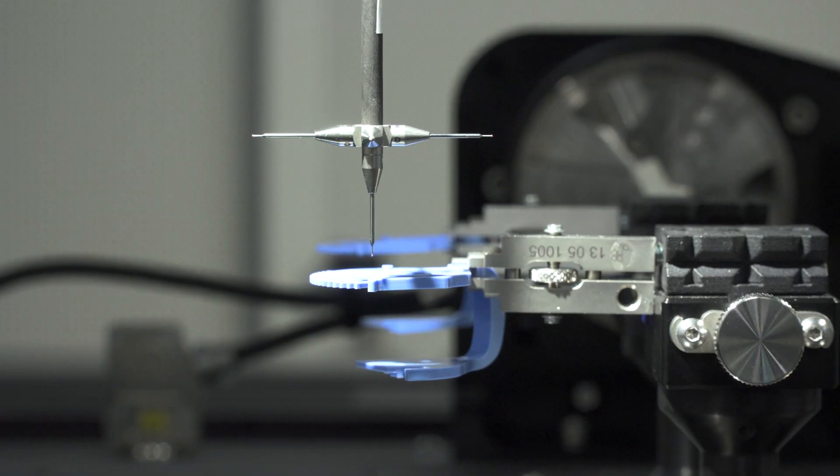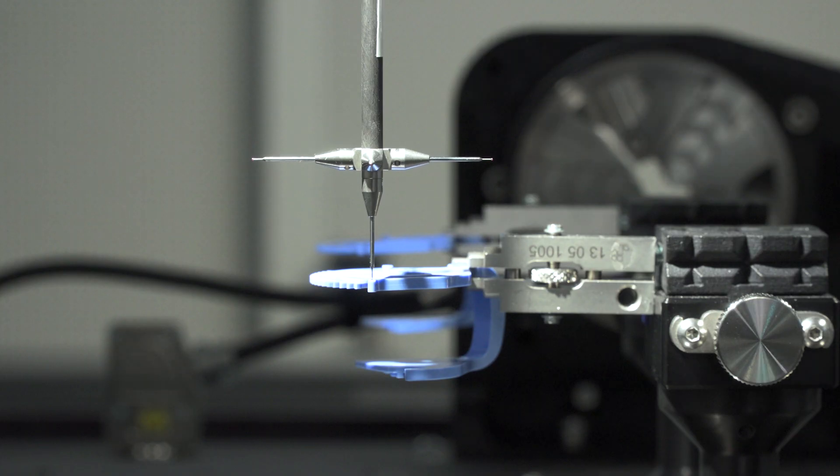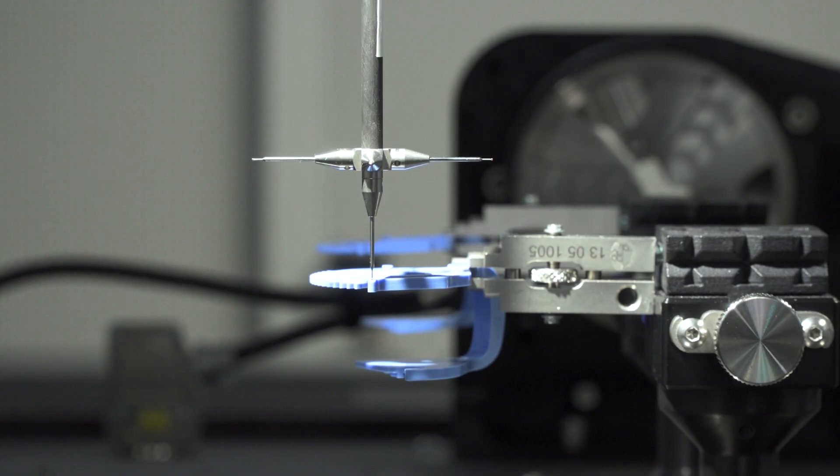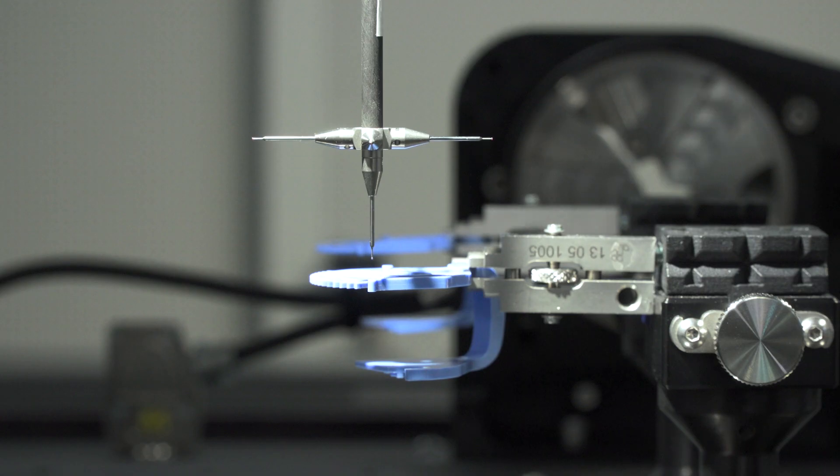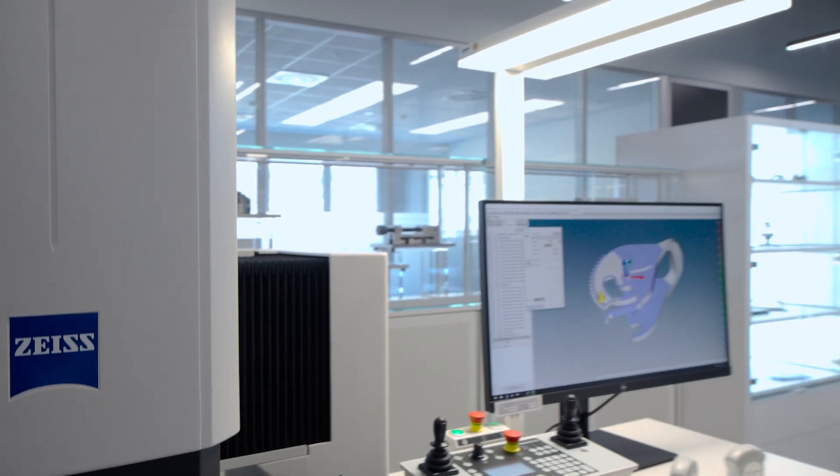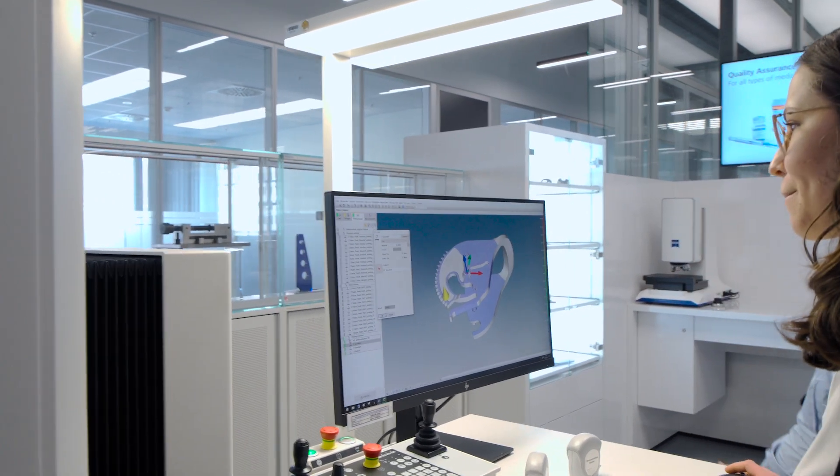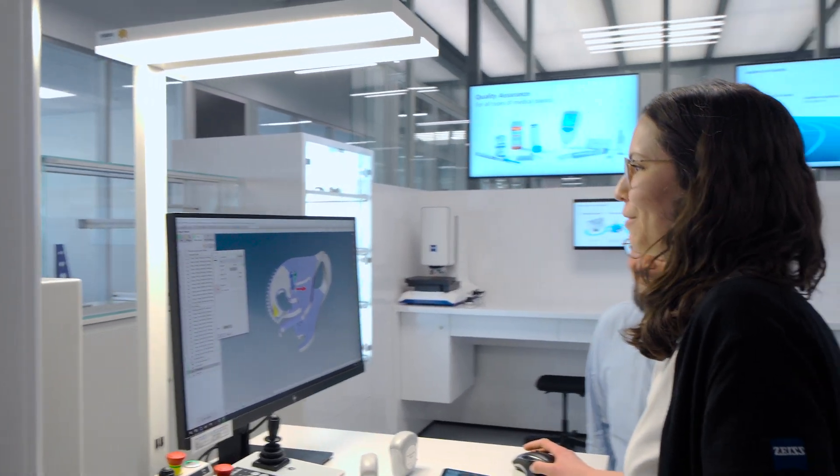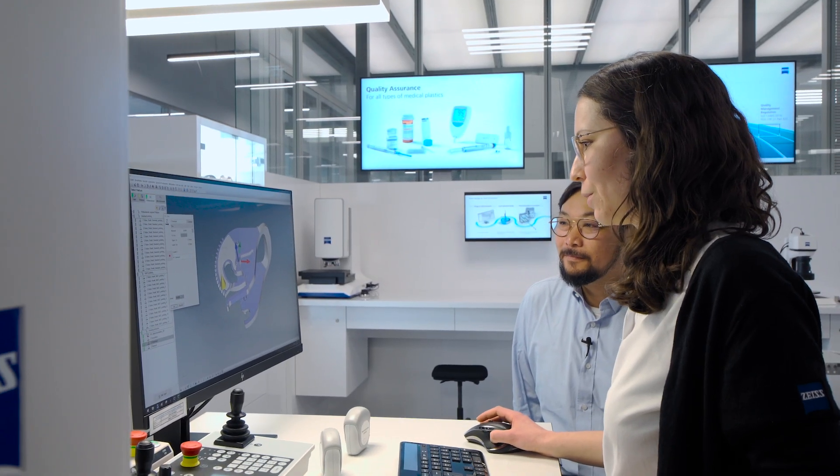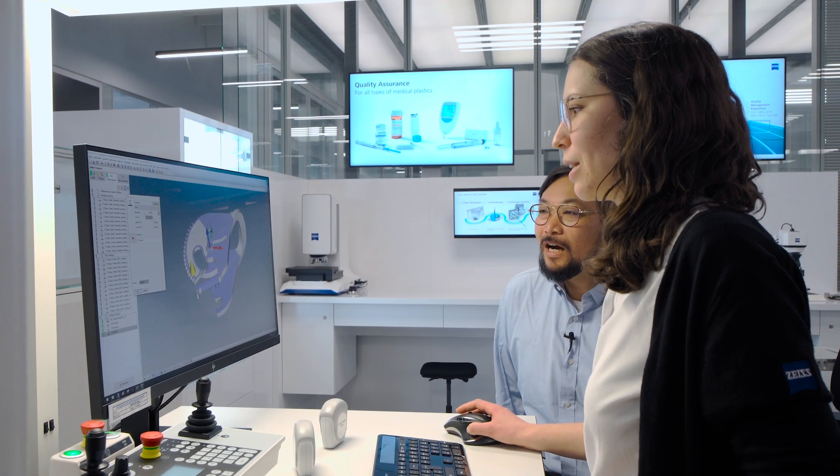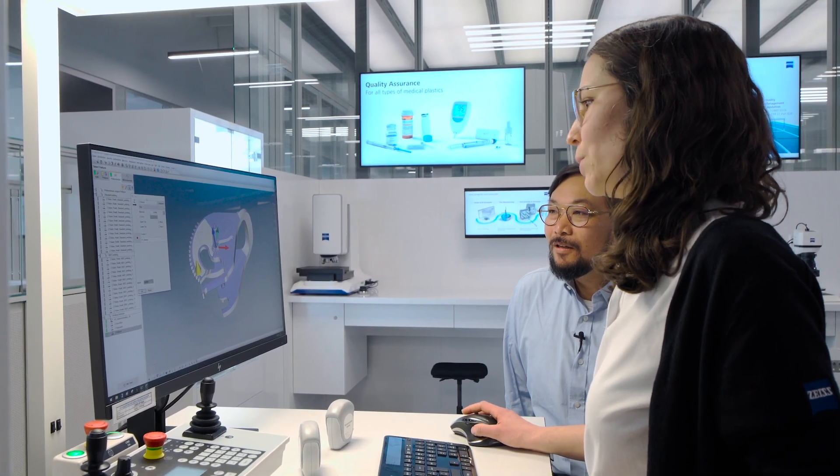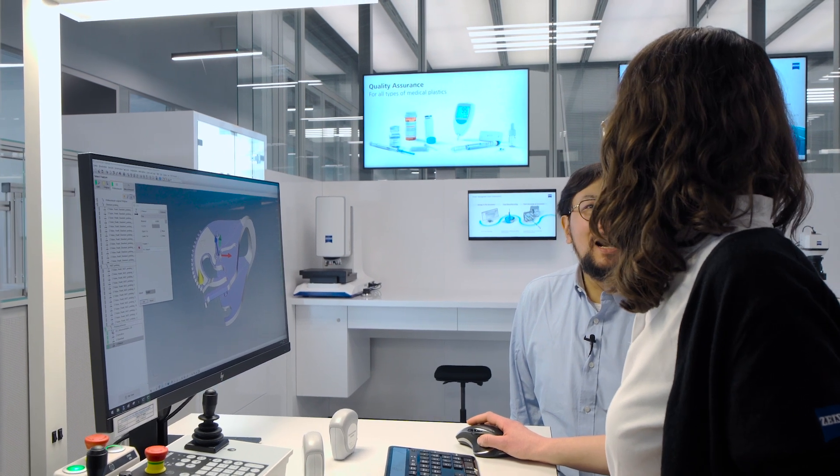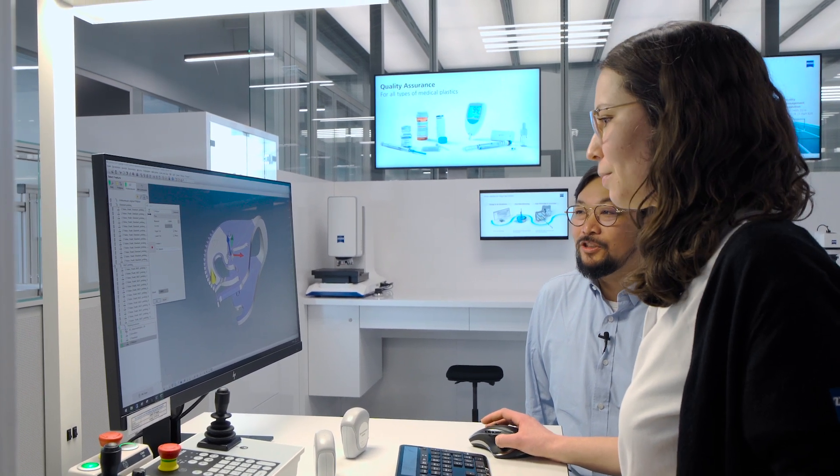You know, just looking at it, it's hard to tell a difference. Yeah. You can't see it, but you can see it on the measurement results. If you check the Z values here, so for sensitive mode, it's around 0.5 micron. Right. Like nothing. Yeah. For our standard mode, we have minus 20 micron. Wow. And robust, we have even minus 40 micron. Wow. So, we see a difference here.